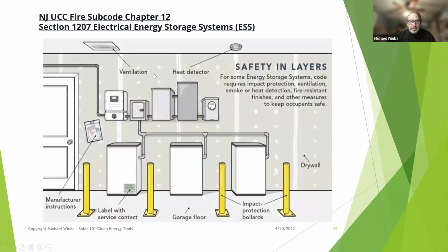So just a little bit about code issues, and this is really a lot different than just solar on your roof. This is the section of the code where you find electric energy storage. You need fireproof containers. You may need bollards if you put it in the garage so you don't run into them. That drywall has to be fire rated insulation. In addition to a smoke detector, you have to have a heat detector and ventilation. And this is a changing area in terms of the electric code. As technology changes, they're changing this portion of the code.